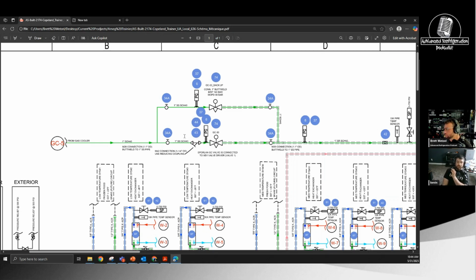Okay, so but that's just the before valve - coming from the gas cooler is a ball valve and a strainer. Okay, there's a Castell strainer on there. So then you have 2 GCVs with ball valves on both sides of them and bleed down taps. Perfect, works awesome.